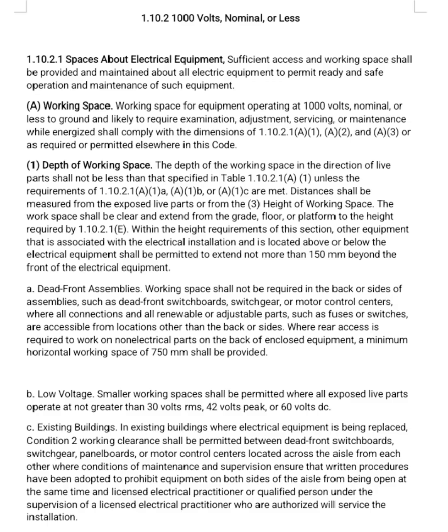The workspace shall be clear and extend from the grade, floor, or platform to the height required by 1.10.2.1E within the height requirements of this section. Other equipment that is associated with the electrical installation and is located above or below the electrical equipment shall be permitted to extend not more than 150 mm beyond the front of the electrical equipment.